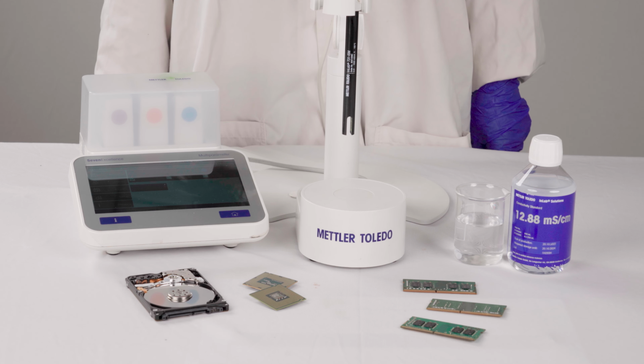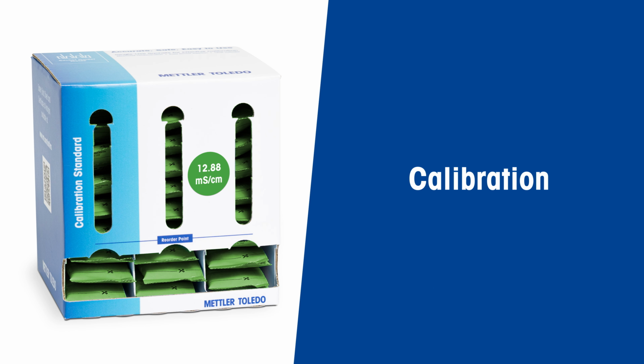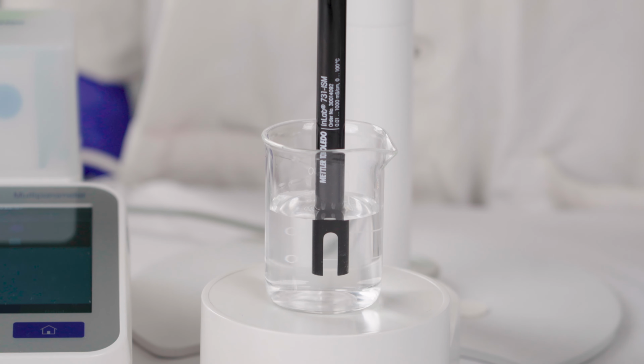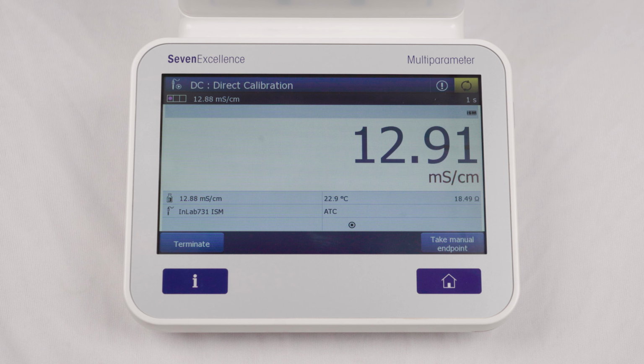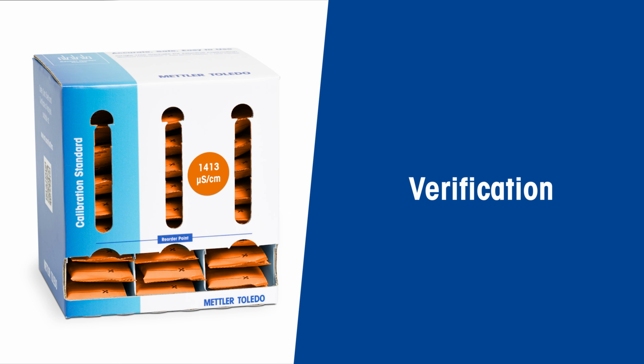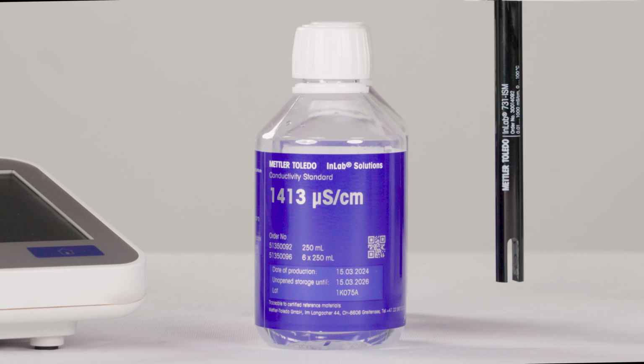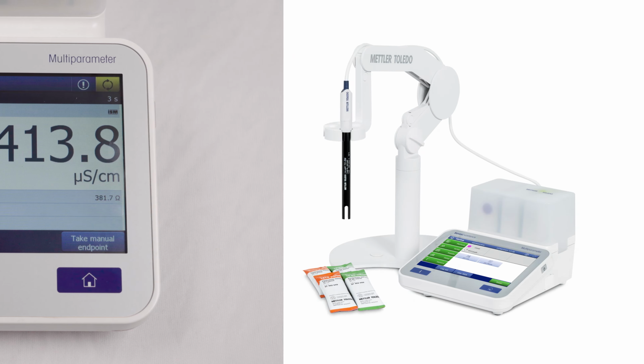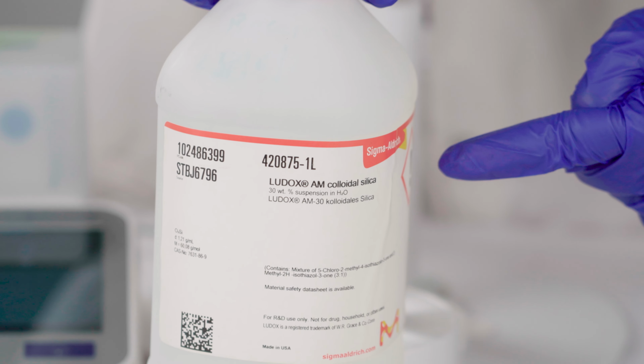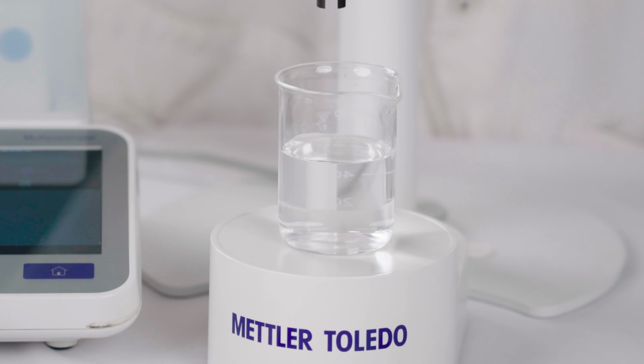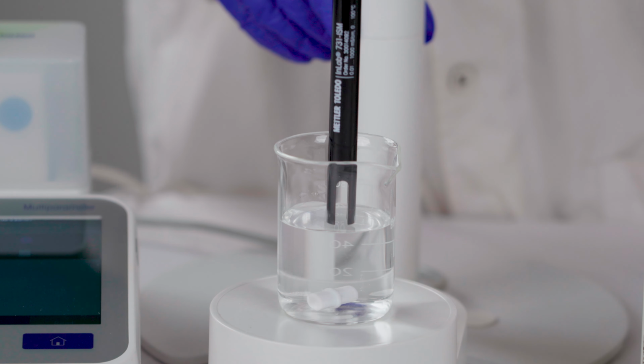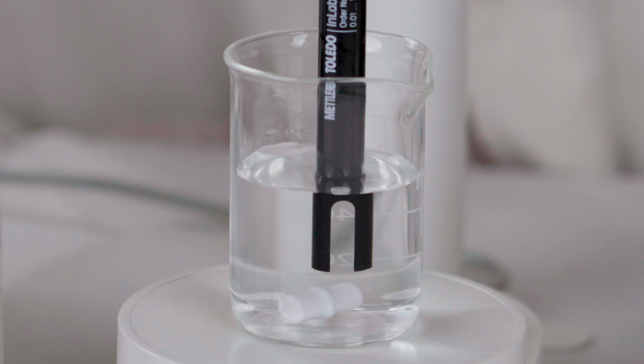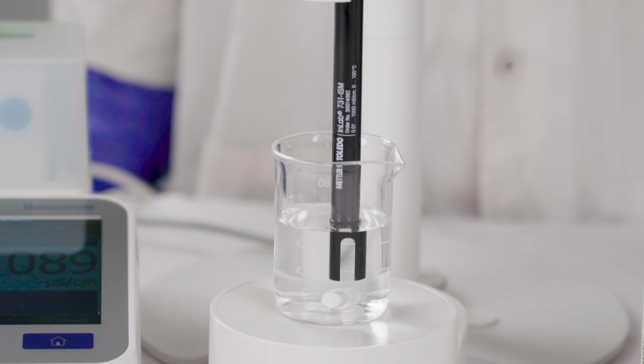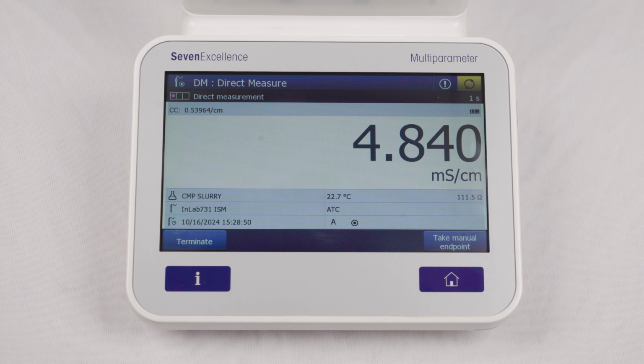Moving on to conductivity measurement. Before your first use, make sure to calibrate your InLab 731 ISM sensor using a METTLER-TOLEDO conductivity standard. And to keep things on track, verify your sensor each working day with a known standard that's different from the calibration standard and close to the expected sample value. Now let's take measurements. First, place your CMP slurry sample in a beaker and carefully immerse the sensor in the center of the sample. Remember to avoid touching the walls or bottom of the beaker. Give it a gentle stir and record the conductivity reading.